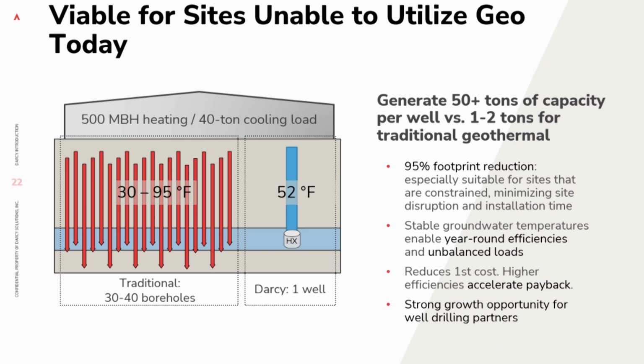Many of our early projects are in the urban environment, and we've seen a 95% footprint reduction. We're also seeing stable groundwater temperatures because of flow in the aquifer, instead of a well field that might migrate from 30 to 95 degrees throughout the seasons. In Minnesota, we see a consistent 52 degree groundwater temperature throughout summer and winter, which allows for unbalanced loads, as well as heating-only or cooling-only applications, like data centers.